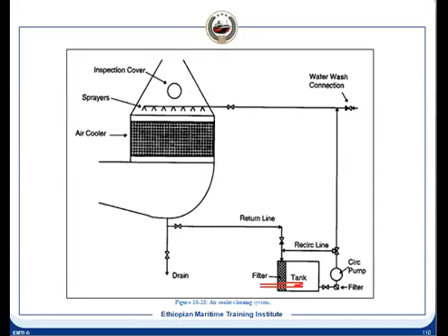We check the differential pressure. That's why there is a manometer. Inlet and outlet pressure is measured, and if the differential pressure increases, it means there is fouling in the air side. So we must clean that.